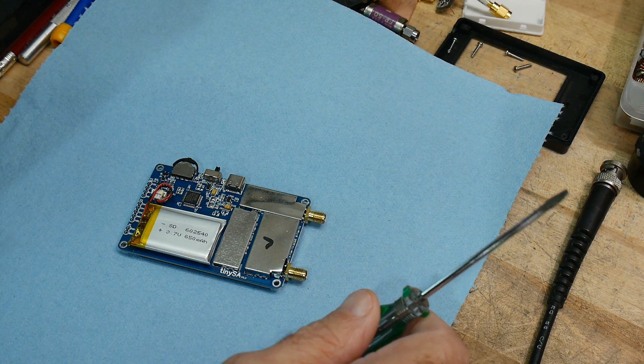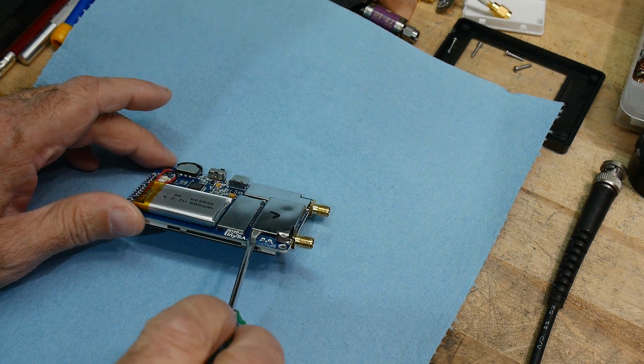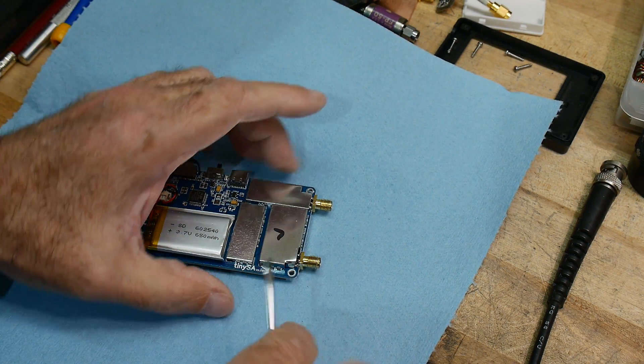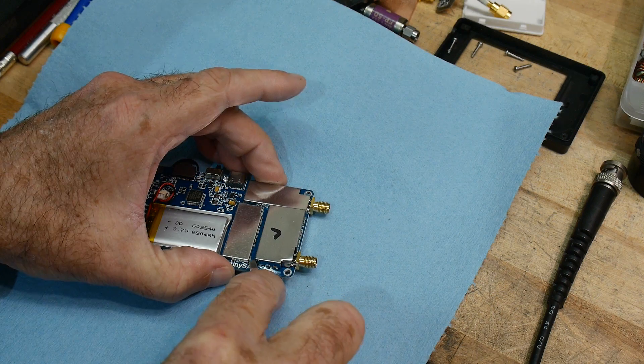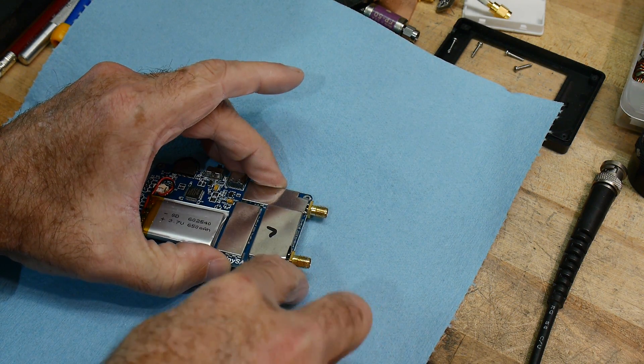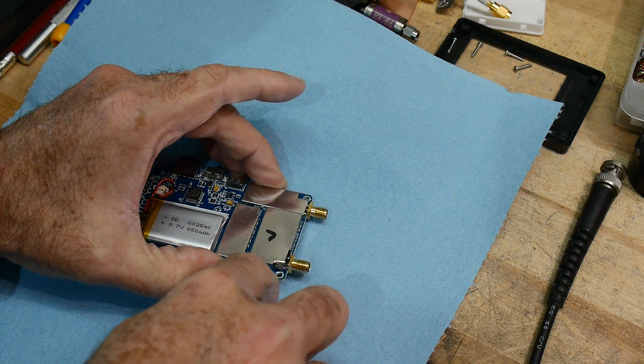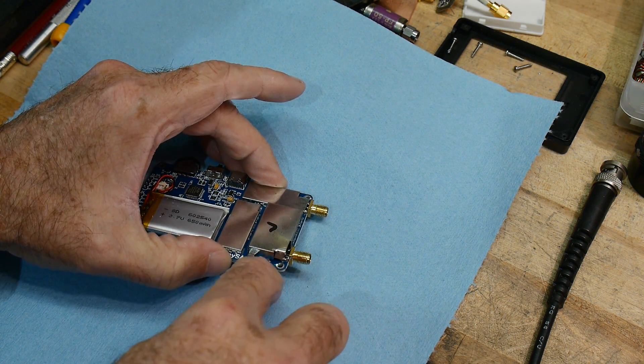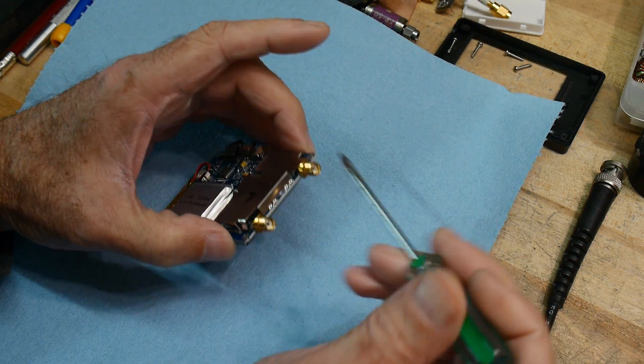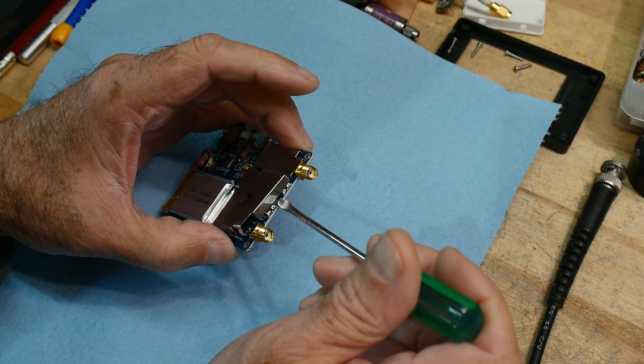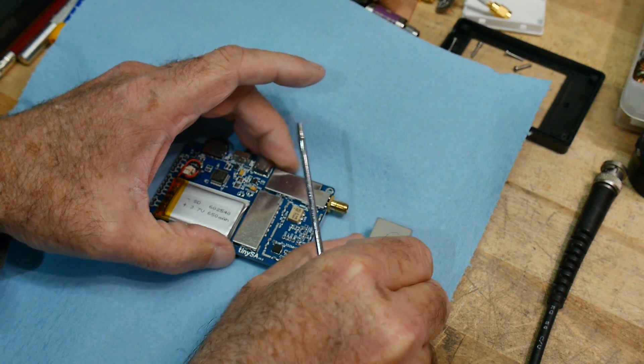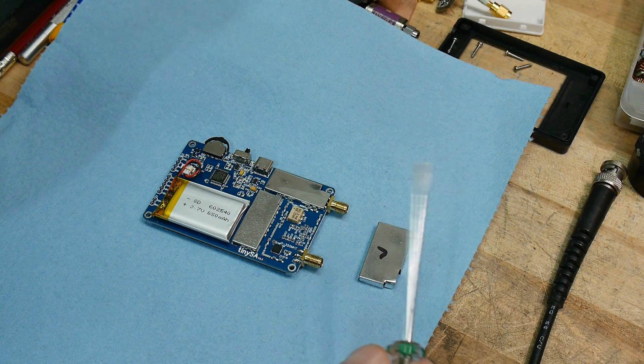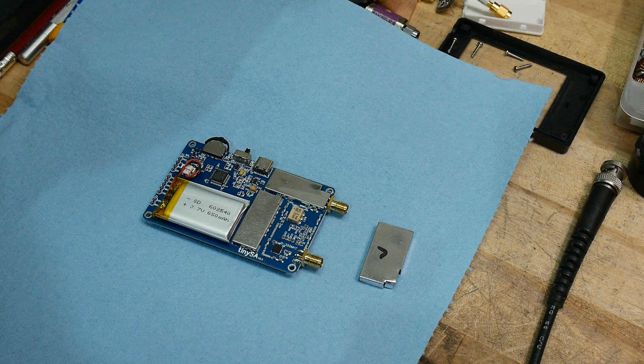All right, let's do some failure analysis. Let's figure out why this attenuator fails at 4 dB. I'm sure everybody knows my story, but this particular TinySA has a bad attenuator, and its symptoms are that it doesn't know how to do 4 dB. The most likely cause is going to be this chip right here, which is the attenuator.